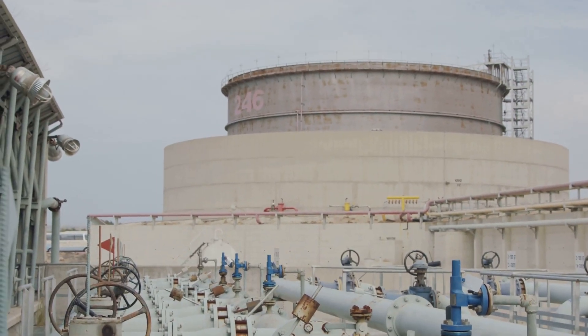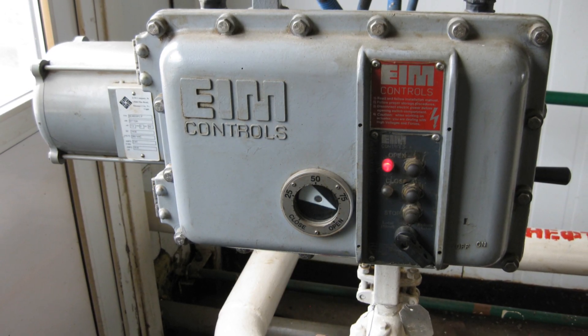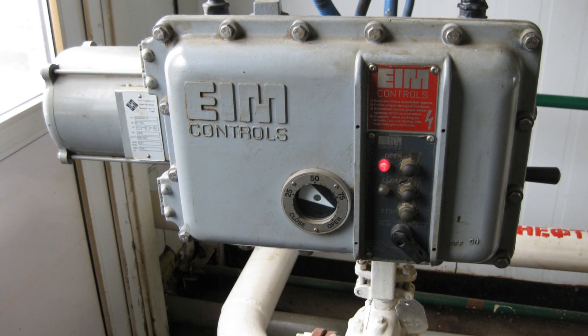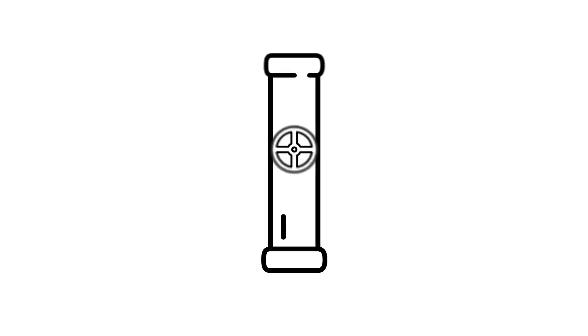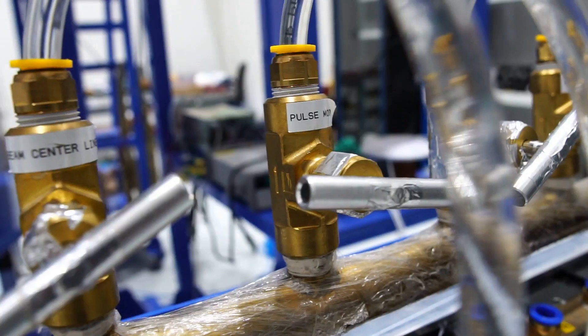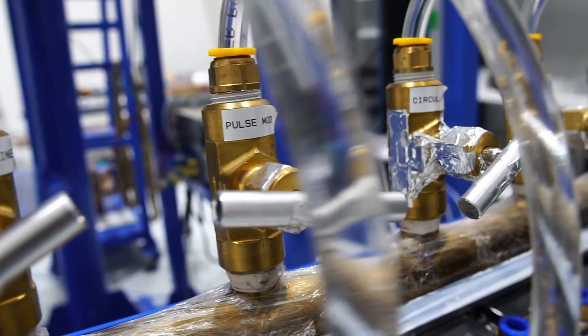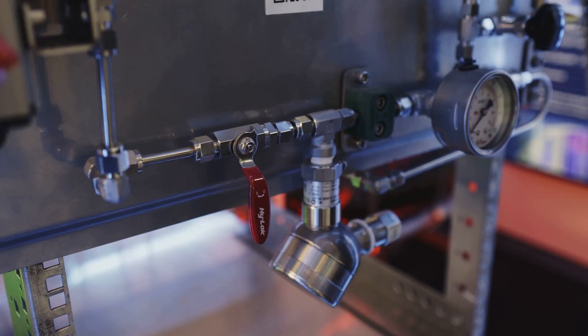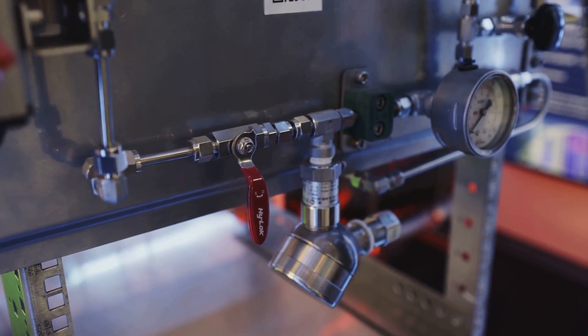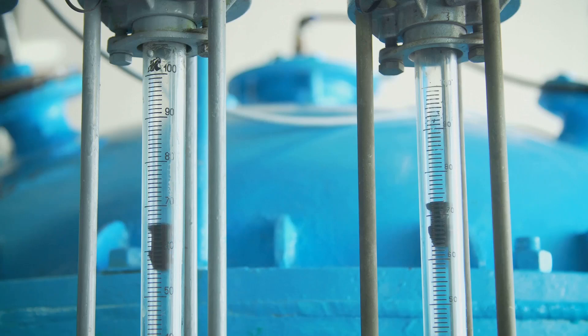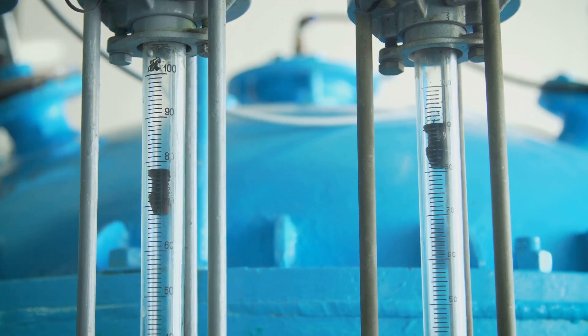The step-by-step working of a control valve: One, signal received — the control valve receives a control signal from a controller like a PLC or DCS. Two, actuator movement — the actuator moves the valve plug or disc to regulate flow. Three, flow adjustment — based on the signal, the valve opens or closes to maintain the desired pressure, flow or temperature. Four, feedback mechanism — sensors provide real-time feedback to the controller. Five, process optimization — the controller continuously adjusts the valve to maintain stable process conditions.